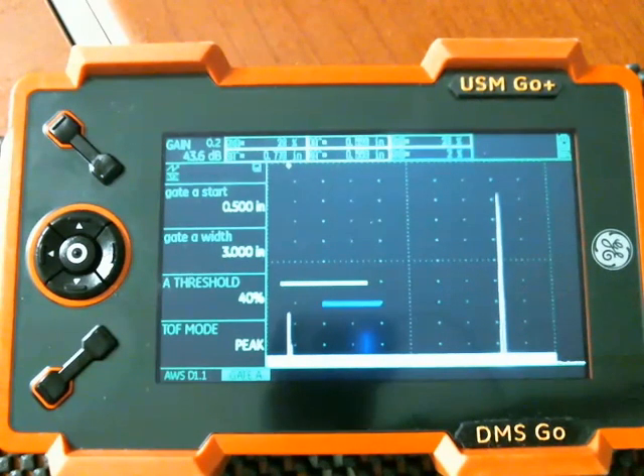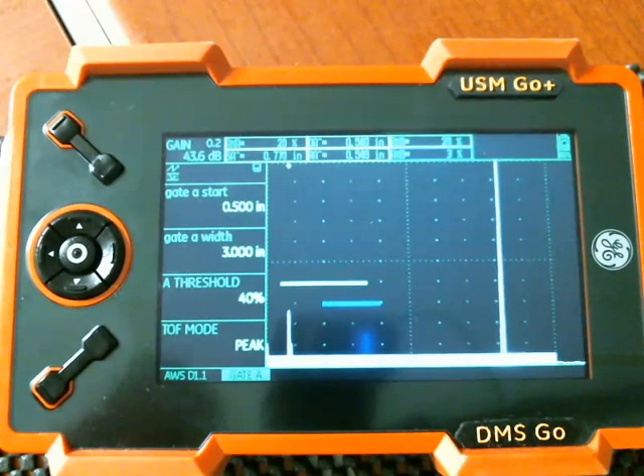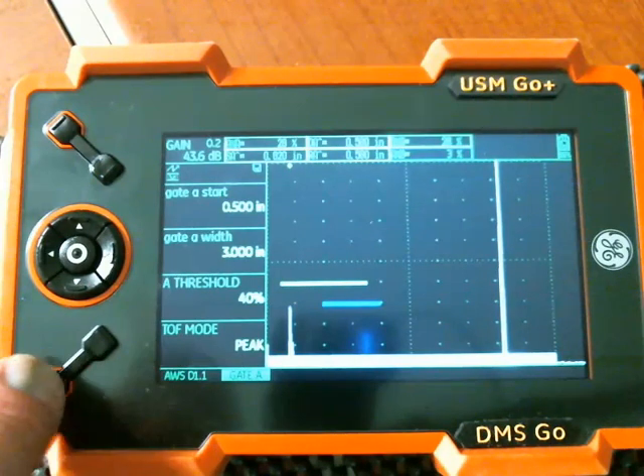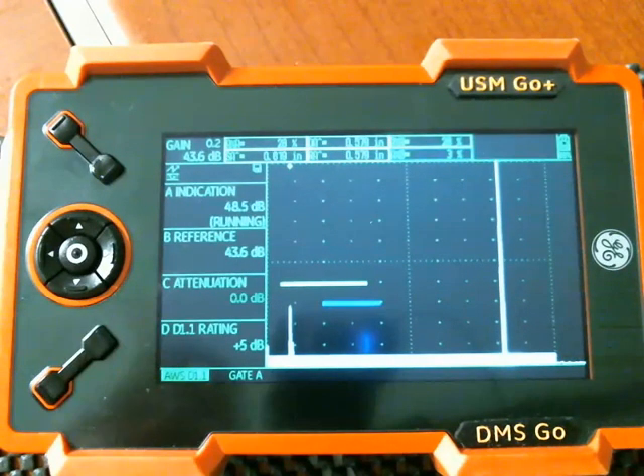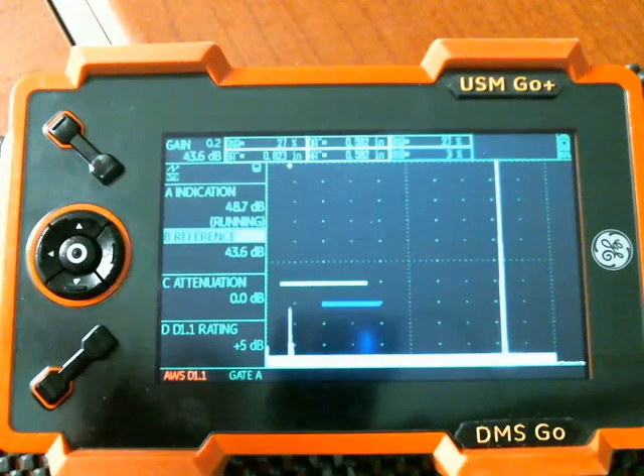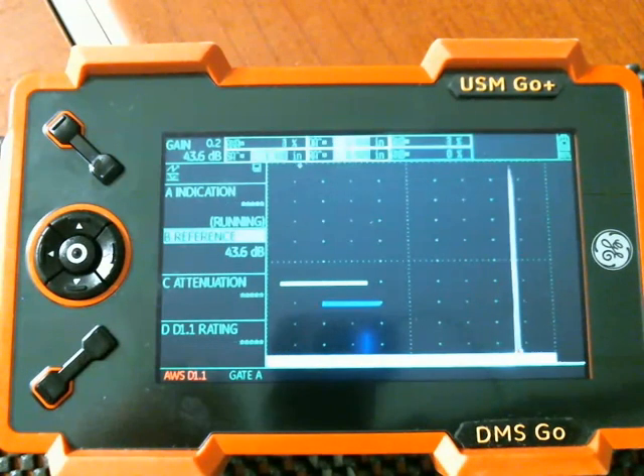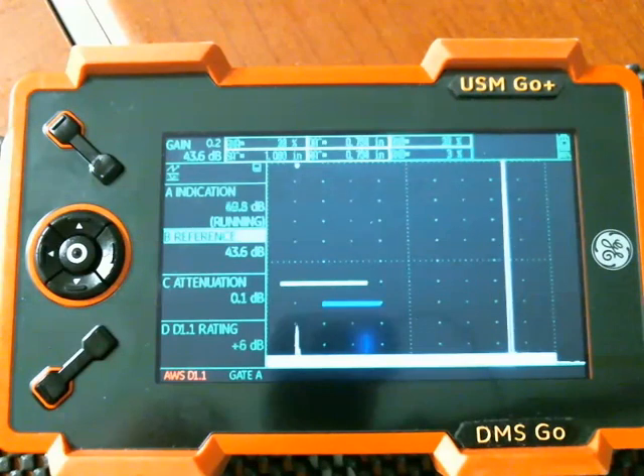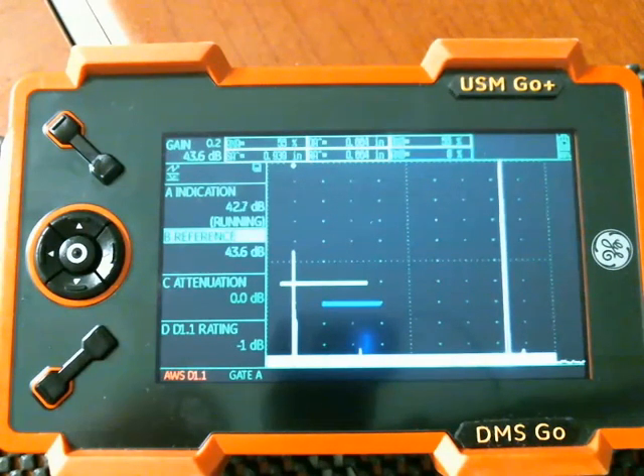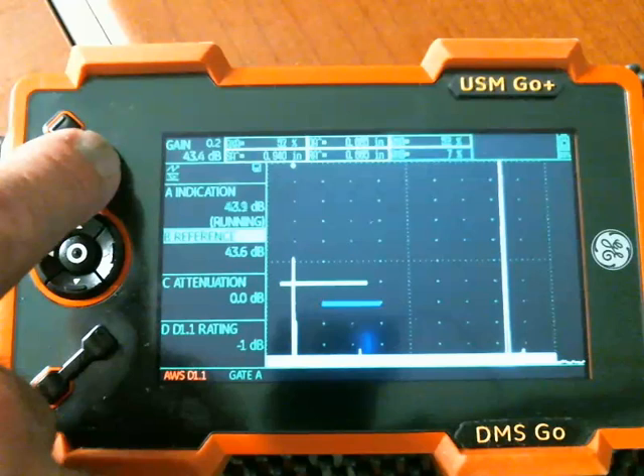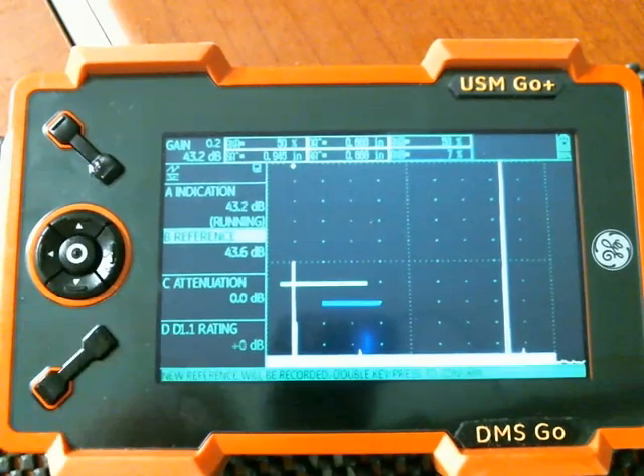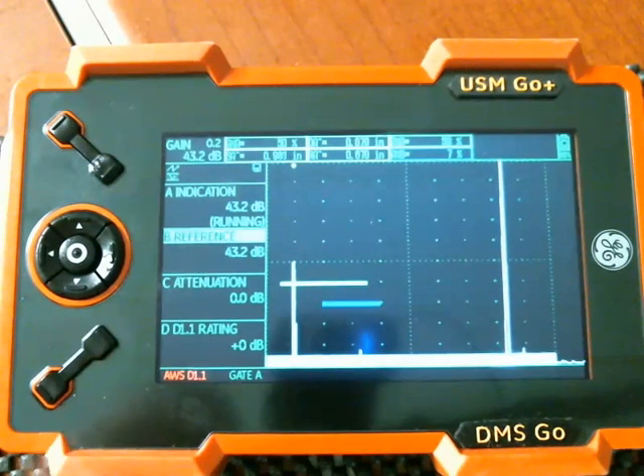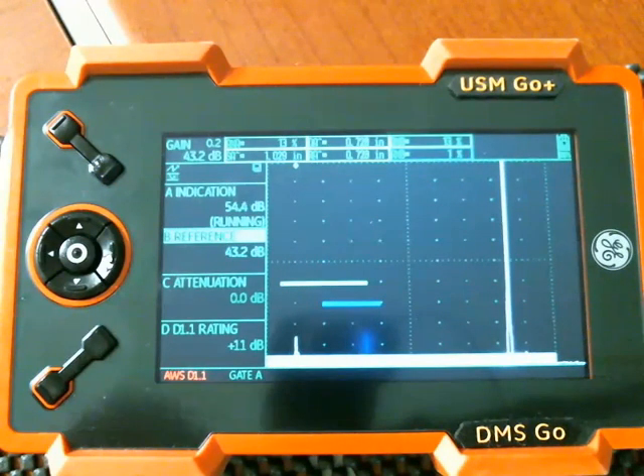I used the gate menu to situate the gate such that I could see my hole on which I want to calibrate. I selected the hole. I peaked up. I came to the AWS menu. I scrolled up to the B reference. Peaked up on the reference echo. Got that at 50%. One right click on the B reference. Double click to accept. And now my calculator is calibrated and running.